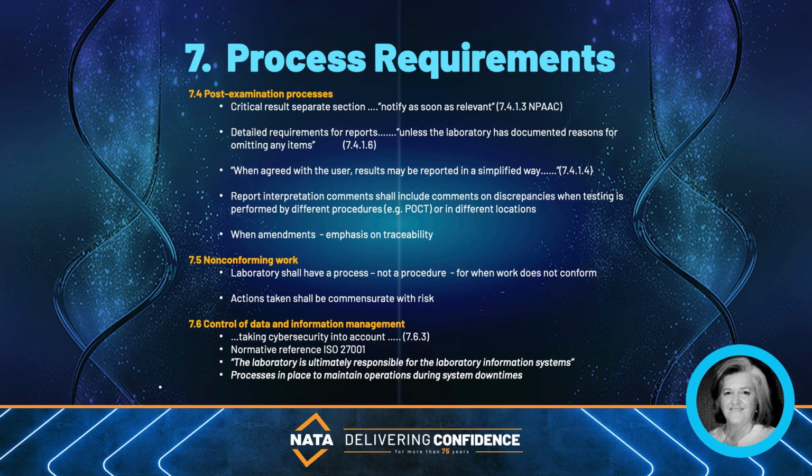Under Section 7.6, labs shall have access to the data and information needed to perform lab activities. The lab is ultimately responsible for the lab information systems. Information systems shall be validated and verified by the lab before introduction, and any changes, including upgrades, shall be documented and verified.